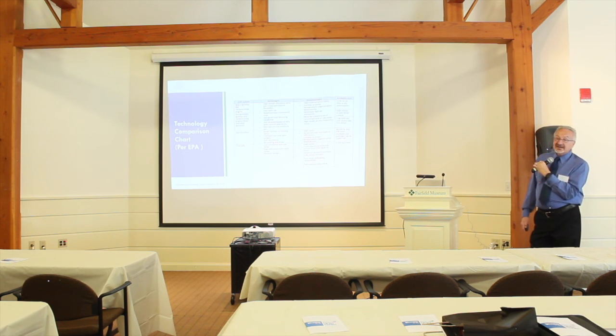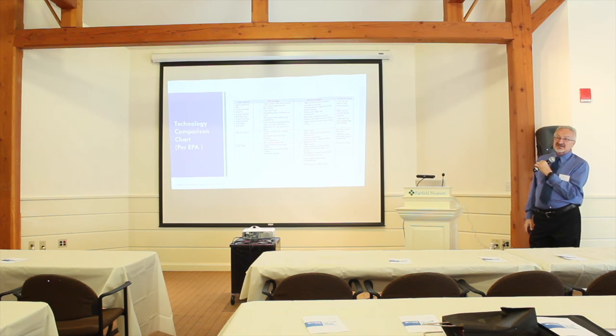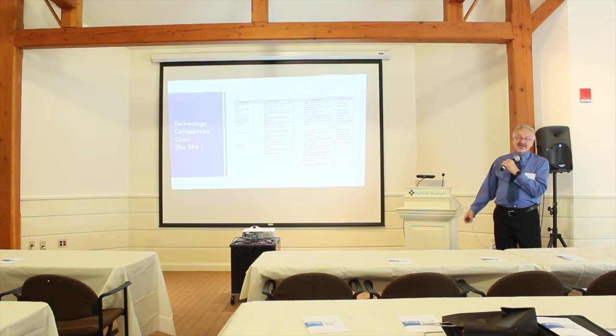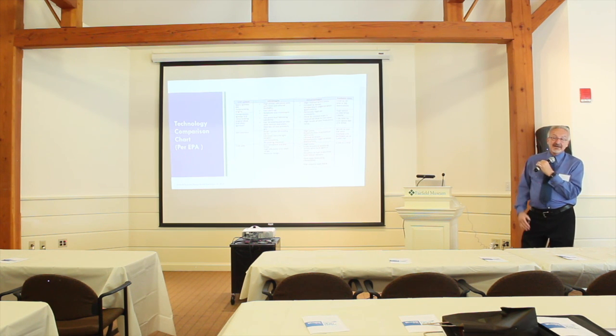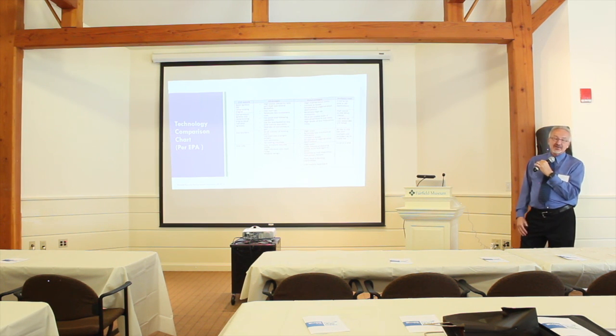Here, EPA has a great comparison for on-site generation to tell you advantages and disadvantages. A lot of times it comes down to a standard old reciprocating CHP system being the best bang for the buck, as I say. There are advantages if you're looking for steam. I have customers where those particular units make hot water, but they have a steam usage, whether it's process. Well, that's going to push you, maybe now you want to look at a microturbine or turbine.